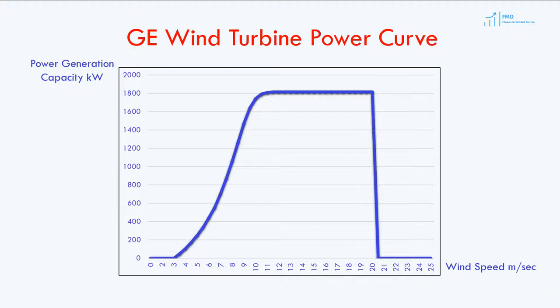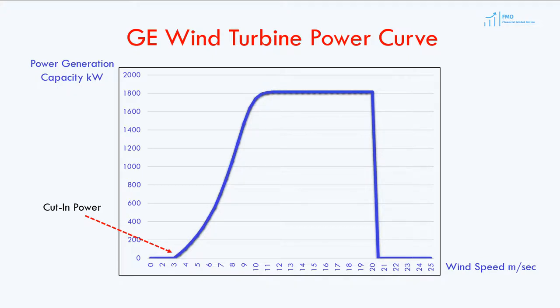First, note that there is no energy output at wind speeds between 0 and 3 meters per second. The wind turbine starts energy production at a wind speed of 3 meters per second — this point is known as cut-in power. At speeds above 3 meters per second, the power output rises until the wind speed reaches 11 meters per second, at which point the power output reaches its maximum level of 1,815 kilowatts. This point is known as rated power.